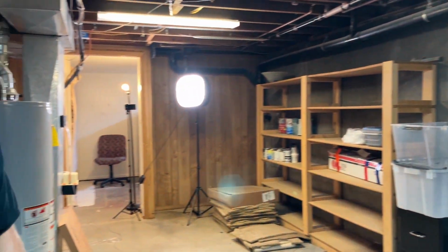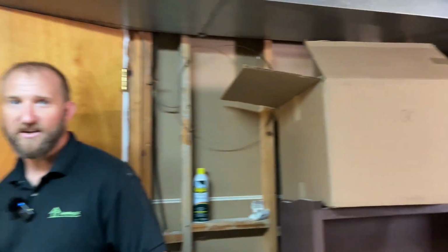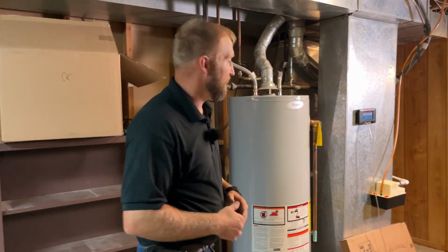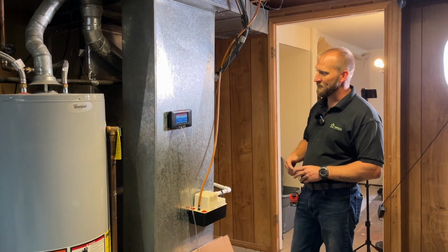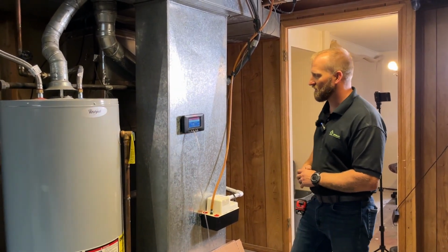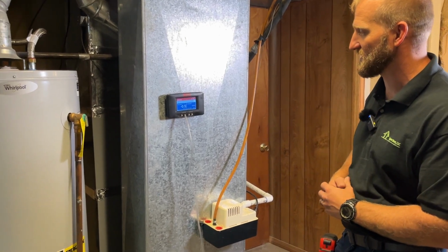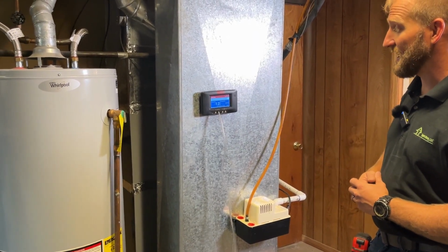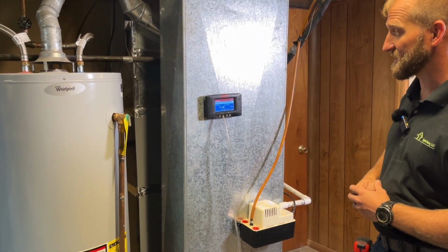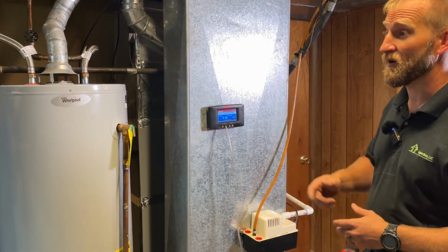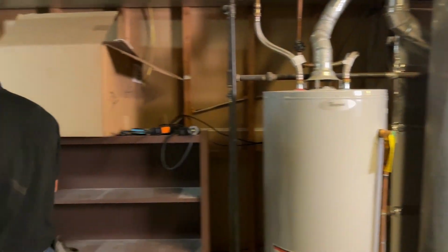In the CAZ here, we're going to check with the CAZ door closed and with it open to see what gives us the worst depressurization. So now once you have your fan running, we're going to see what our worst case depressurization is with the door open and door closed, as I said. It actually looks like it's pressurizing slightly down here with the fan running. So I'm going to open up this door here.